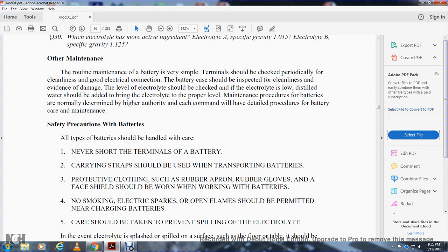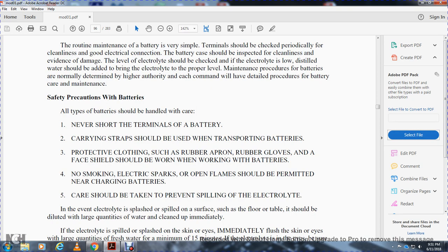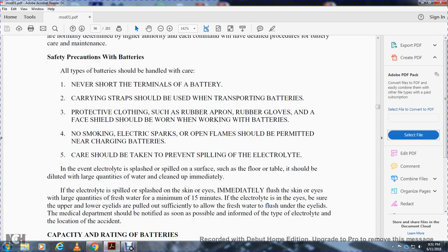Safety precautions for batteries: all types of batteries should be handled with care. Never short the terminals of a battery. Carrying straps should be used when transporting batteries. Protective clothing — rubber apron, rubber gloves, and face shield — should be worn when working with batteries. No smoking, electrical sparks, or open flames should be permitted near charging batteries. Care should be taken to prevent spilling electrolyte.